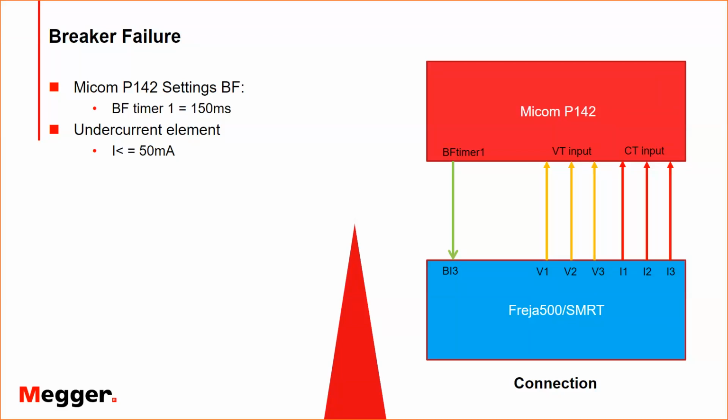So when I want to do a test for this, I will test first the breaker failure timer. I will give initiation to my breaker. I will give a contact back, a binary output, to my relay. I should have drawn that in the diagram here. And this contact will force breaker failure to initiate. It's like an external trip. Let me draw that very quickly for you.